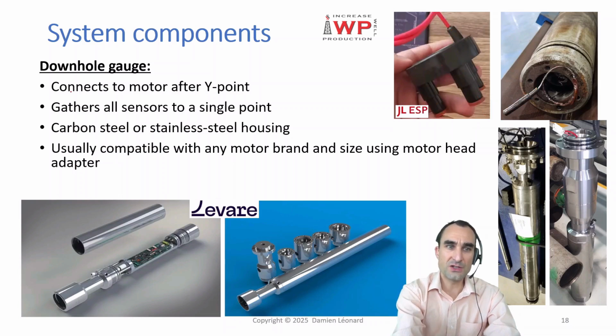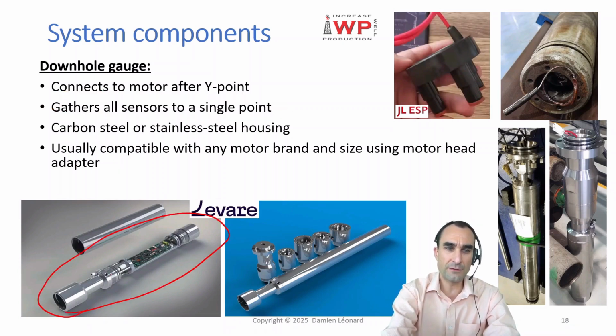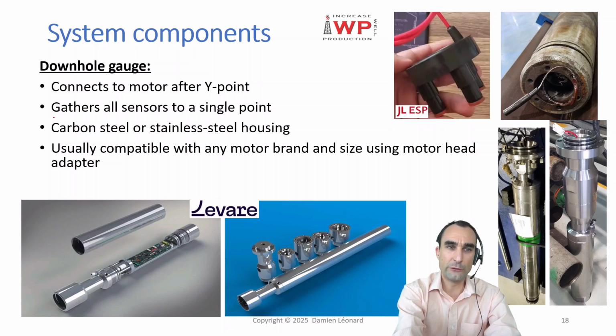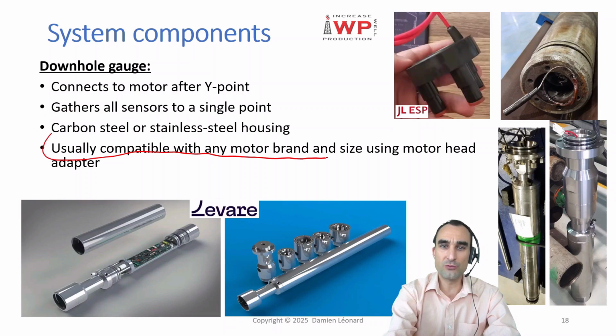The downhole gauge gathers all the sensors to a single point. Inside of your gauge, you're going to have one sensor for each of the parameters being monitored by your gauge, and each of these sensors will be powered through this single cable over there. In terms of material, the gauge typically comes with a housing of carbon steel or stainless steel, and it is usually compatible with any motor brand and size using a motor head adapter.